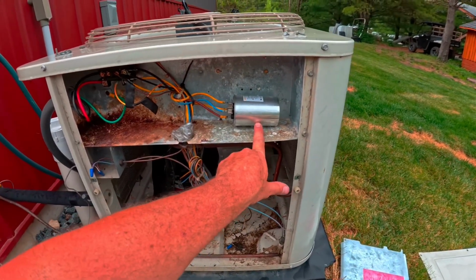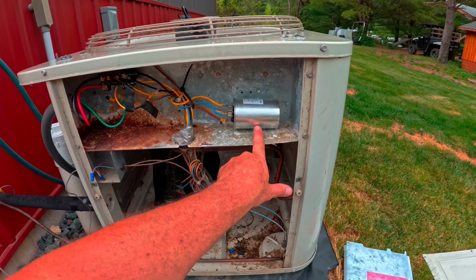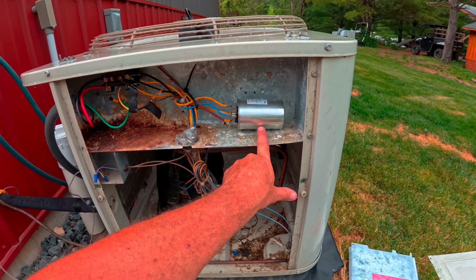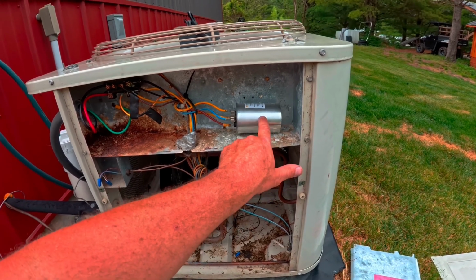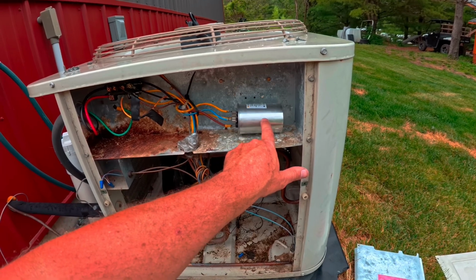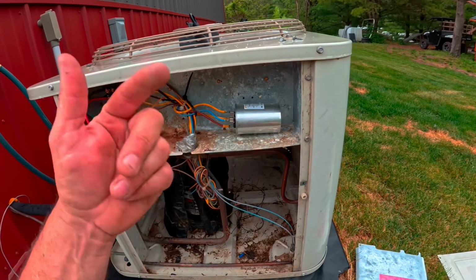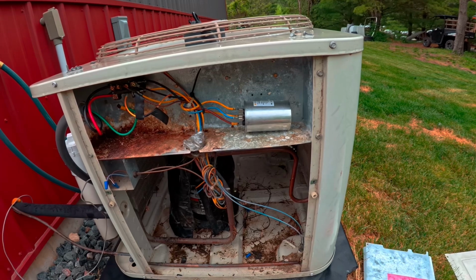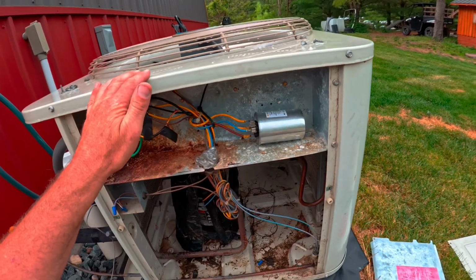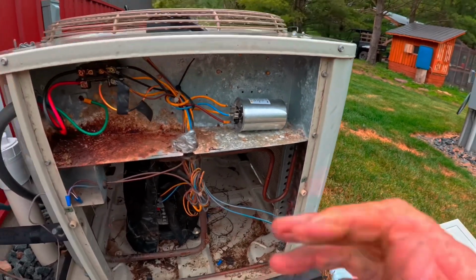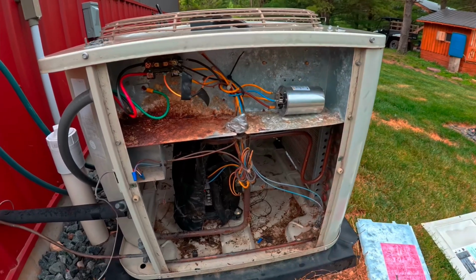This capacitor stores energy. So when the fan tries to turn on and when the compressor tries to turn on, it takes power from this capacitor and uses it to basically give it a kick in the butt to get the motor going from a dead stop. Once it's up and going, it's good from there. But this helps get it started.